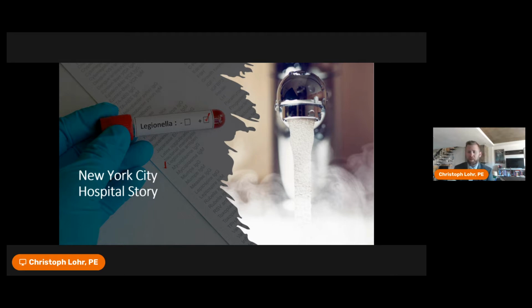Well, after a lot of troubleshooting, in which everything under the sun was blamed, what was going to be determined what the root of the problem was: the hot water return system was never balanced. The hot water return system was out of whack, which led to stagnant conditions all throughout the facility. And in my conversations and giving a version of this presentation, which typically is 1 to 2 hours, I'm condensing a lot of material into a very short amount of time.